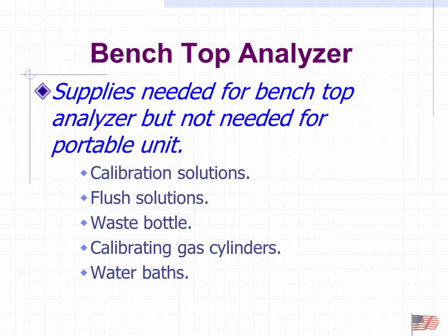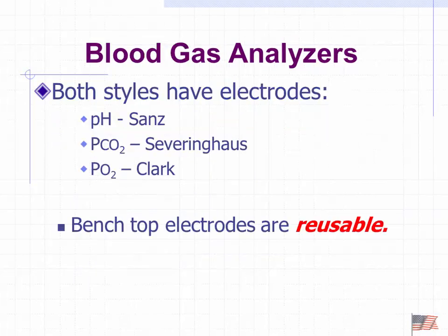Some of the other supplies that you may need for that benchtop, but you don't need for the portable unit. We need calibration solutions and calibrating gases because we're going to do periodic calibrations to make sure the device is operating correctly. We mentioned flush solutions. After each blood gas, we want to flush the system out so it doesn't have anything contaminating it and potentially clotting it up. There's a waste bottle. And water baths, meaning that we keep the electrodes at a constant 37 degrees temperature. So the actual physical electrodes are immersed in a literal water bath to keep them at a constant temperature. Why that's important, I'll get to in a second.